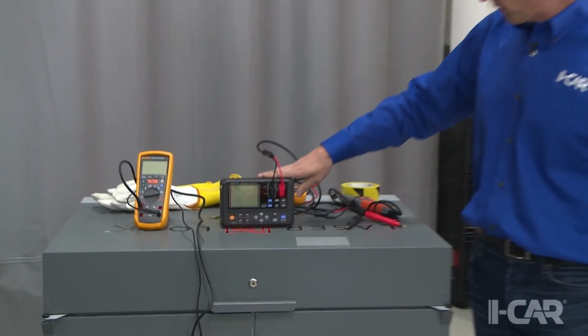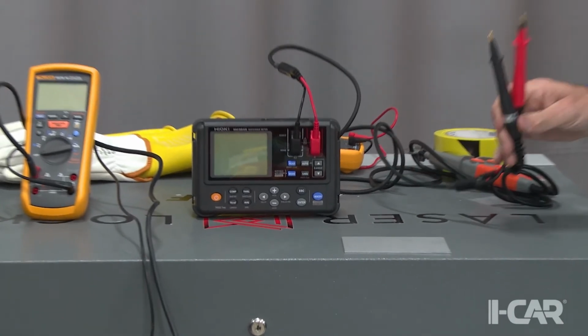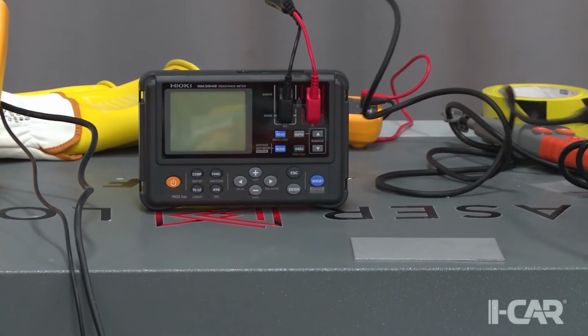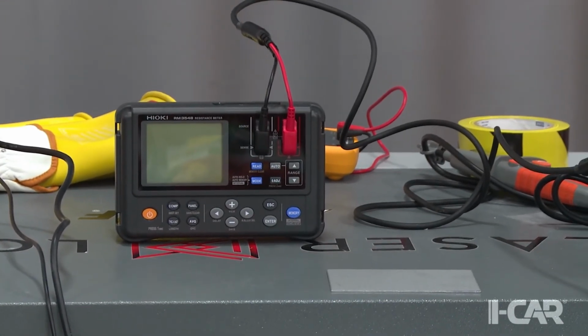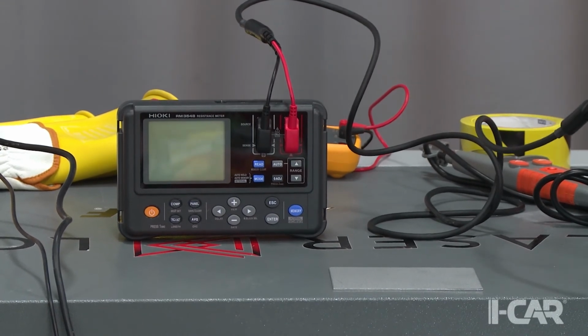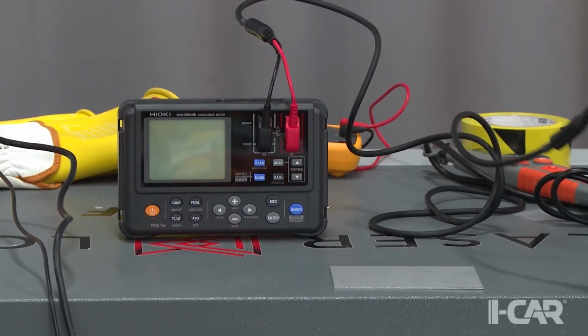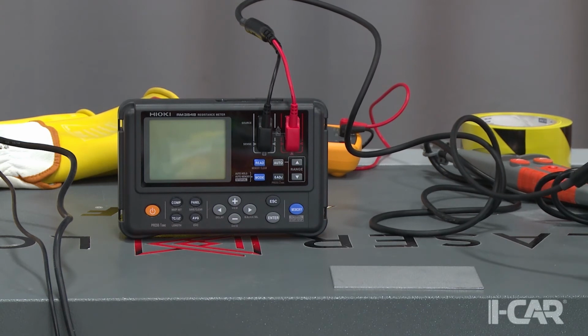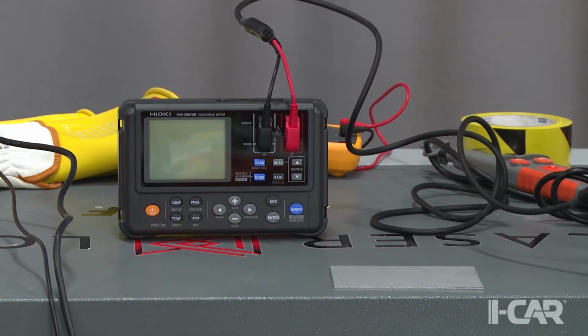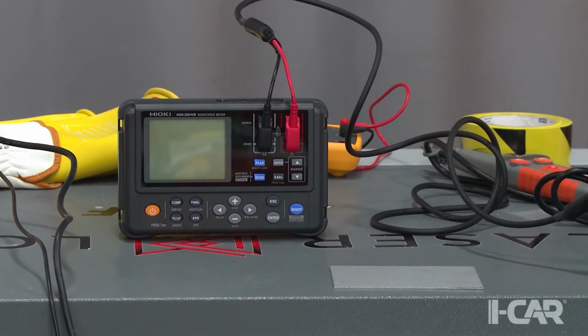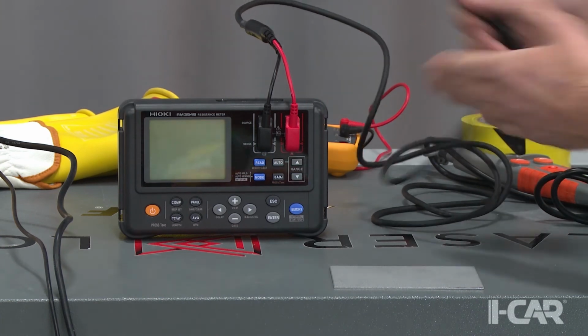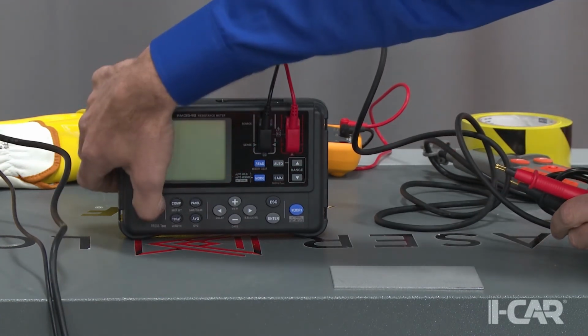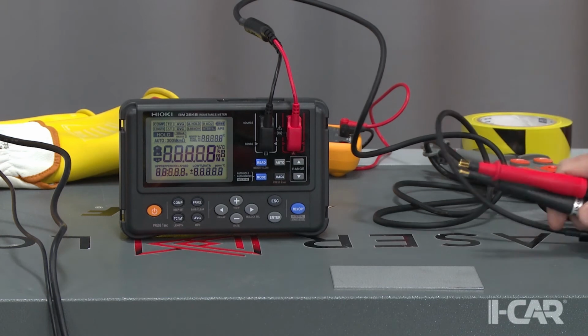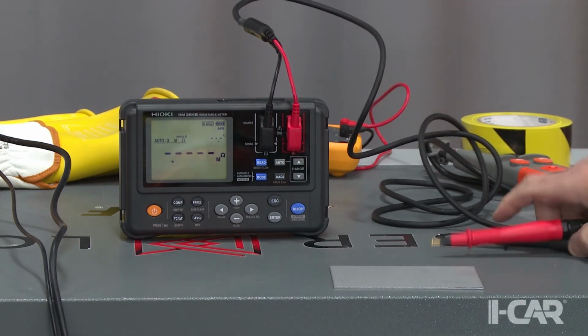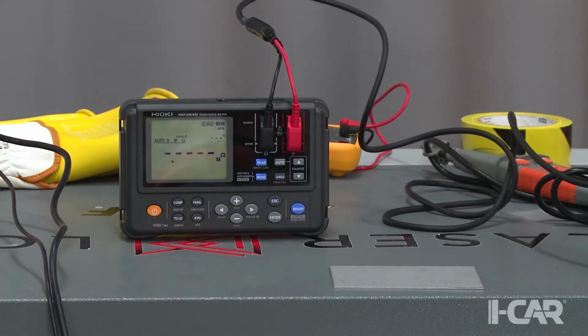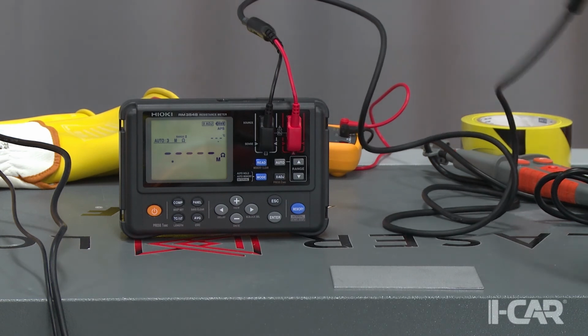What we're doing with this milliohm meter is measuring using what's called a 4-wire measurement method. So we have 4 wires: one is applying a current, a measurement current, and 1 amp is a good measurement current. We don't need a fancy milliohm meter like this one, let me switch it on. It's not actually cheap, but it's really cool and easy to handle.